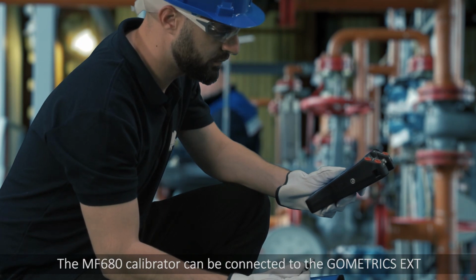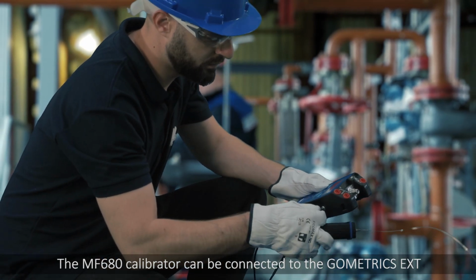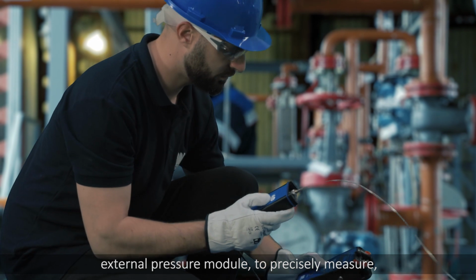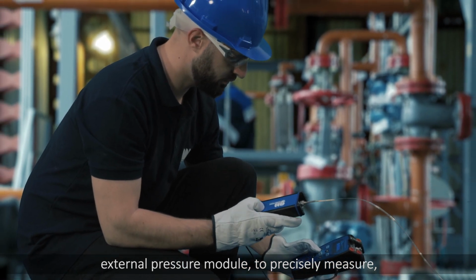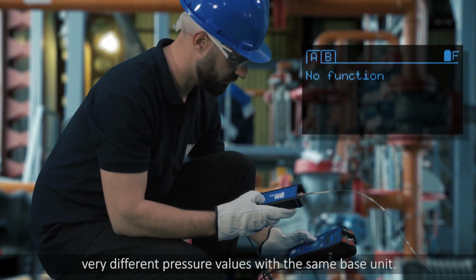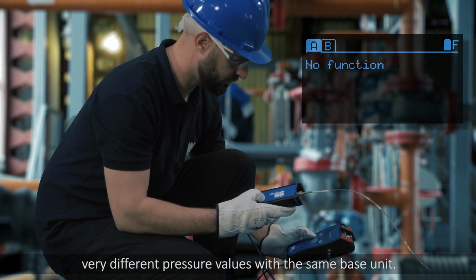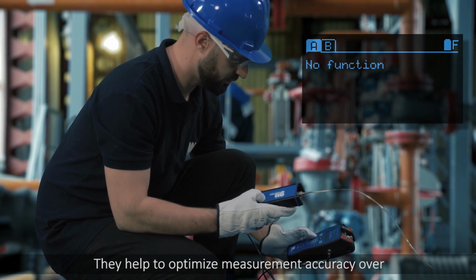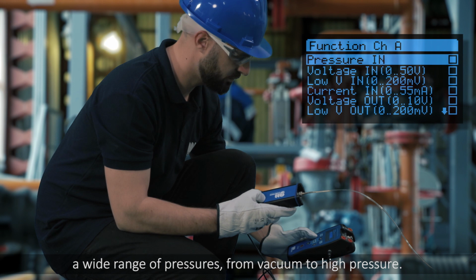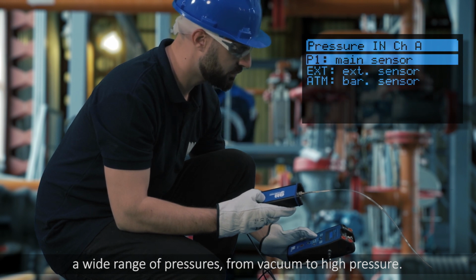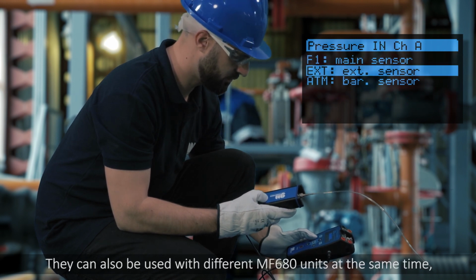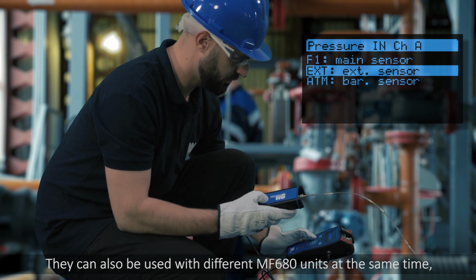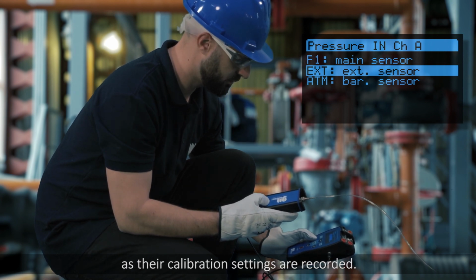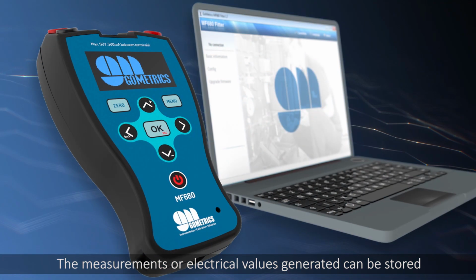The MF680 calibrator can be connected to the Gometrics EXT external pressure module to precisely measure very different pressure values with the same base unit. They help to optimize measurement accuracy over a wide range of pressures, from vacuum to high pressure. They can also be used with different MF680 units at the same time, as their calibration settings are recorded.